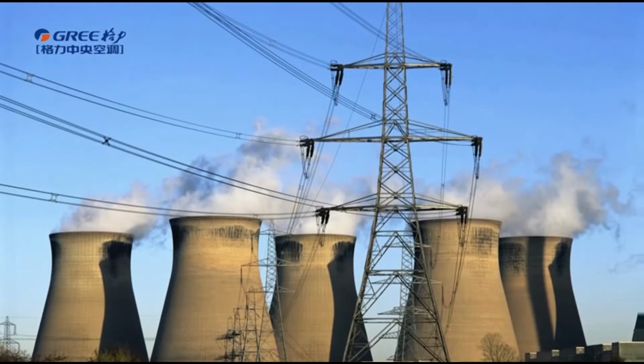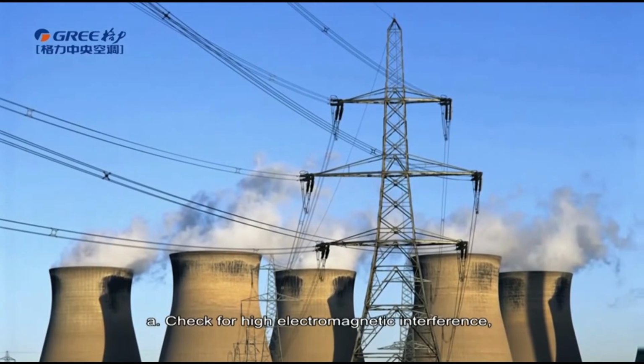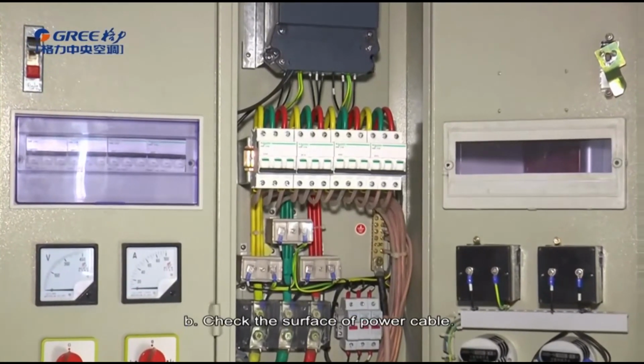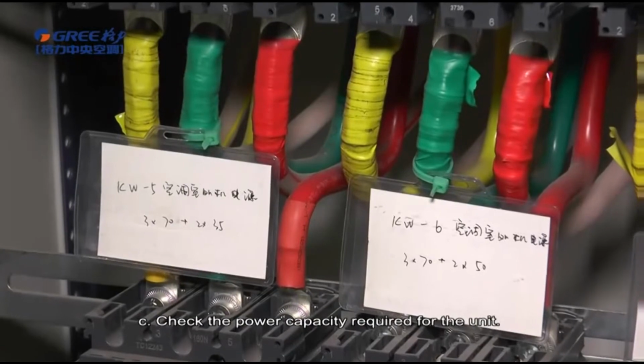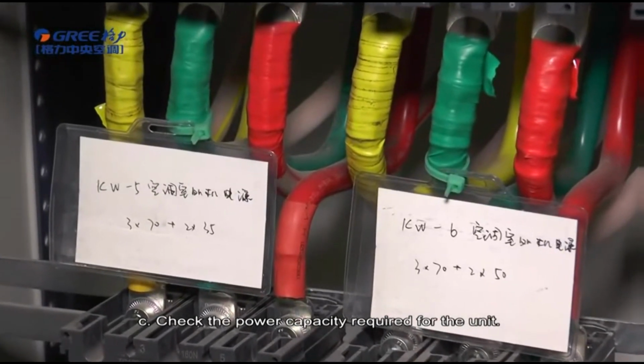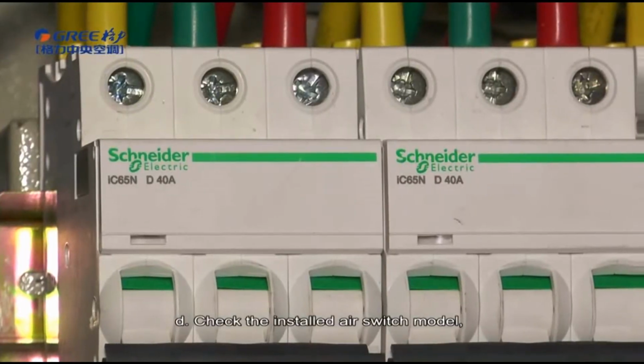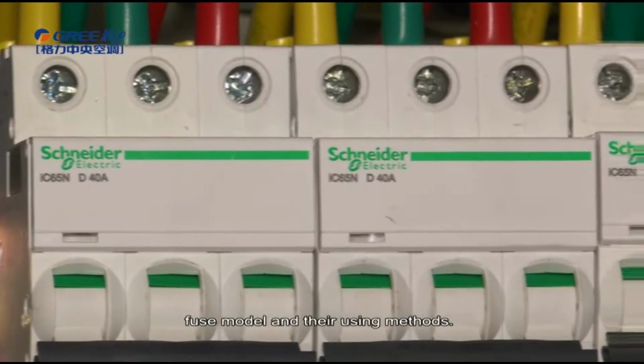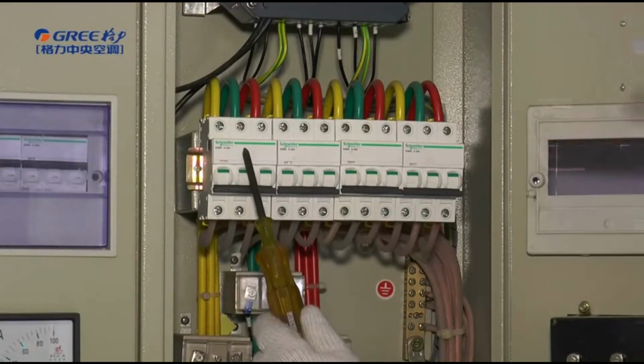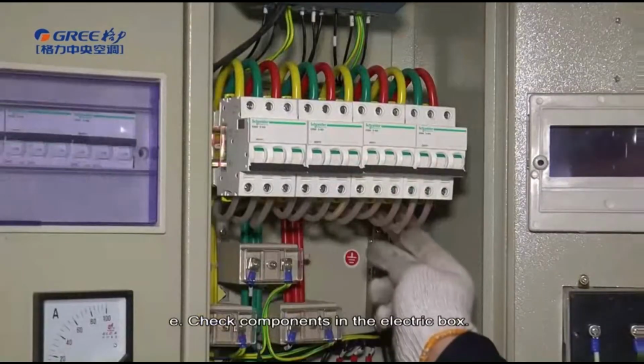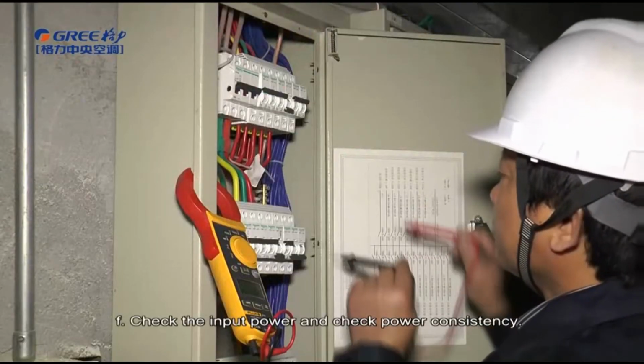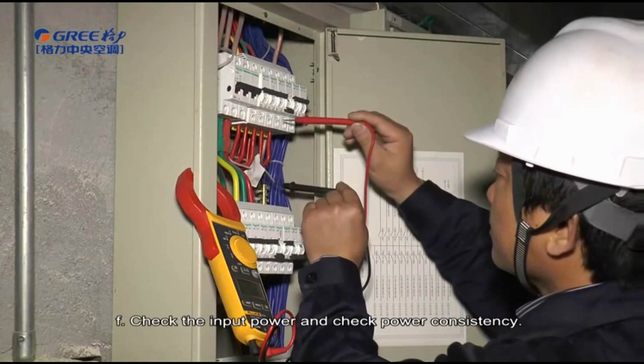Check the electrical system. Check for high electromagnetic interference, dust and acidic or alkaline gas in the operating environment. Check the surface of the power cable. Check the power capacity required for the unit. Check the installed air switch model, fuse model, and their using methods. Check the components in the electric box. Check the input power and check power for consistency.